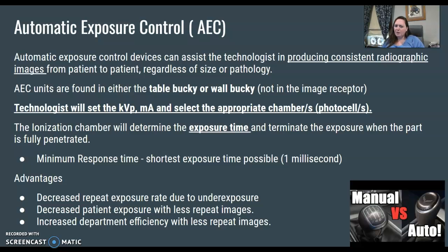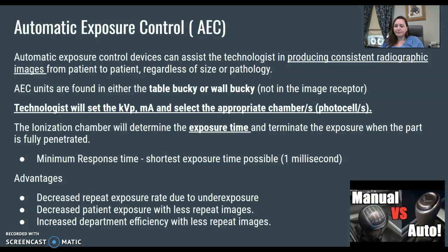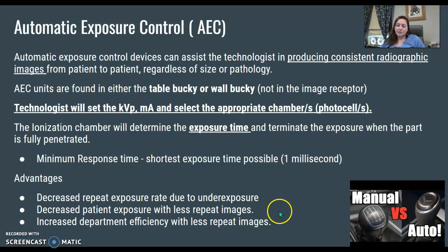There is a minimum response time — it's the shortest exposure time possible, and that's one millisecond. There are a couple of advantages to AEC: decreased repeat rates, decreased patient exposure because you're not trying to determine the appropriate mAs for that patient, and department efficiency with less repeats due to exposure errors.